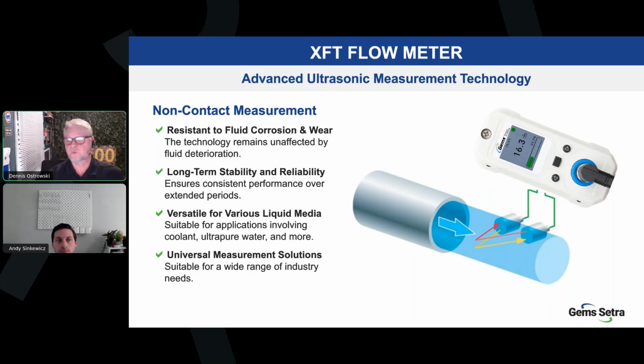Okay, what you see here is a rudimentary image of the operating principle. You have an emitter and a receiver, upstream and downstream, and it's measuring the time of flight for the ultrasonic sound waves to pass through that liquid. Then it does some math inside the device to figure out the difference between upstream and downstream travel, and that's how you get your flow rate. Different liquids have different sound speeds, right? A thicker liquid, the sound's going to travel slower than in a water-based liquid, for instance, right? That's called acoustic velocity. That value can be programmed into the device.